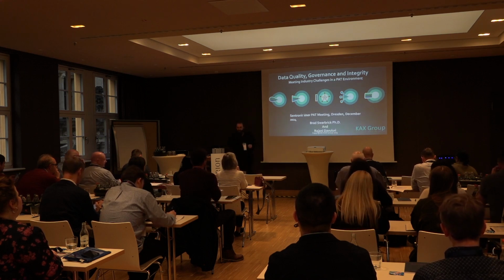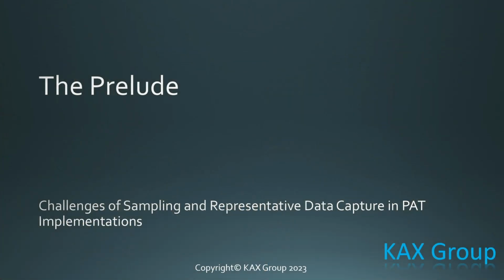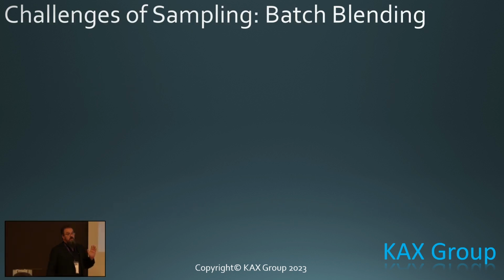So the prelude. We've heard this throughout the entire day. It's a common story that in order to generate good data, our sampling has to be the best that possibly can be. PAT isn't plug and play. You don't just stick a probe in and things work. 90% of the effort is typically put into collecting a sample that's representative or a snapshot of the process at the current time so that you can make a quality decision.